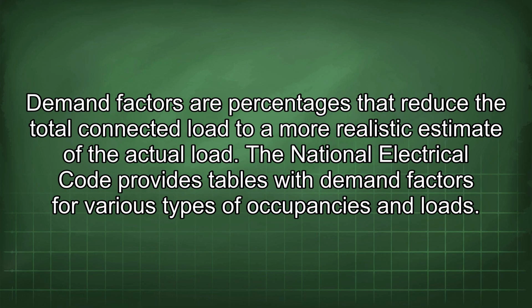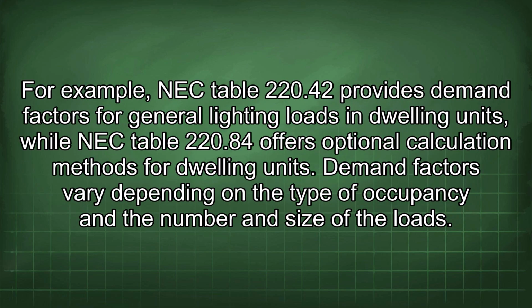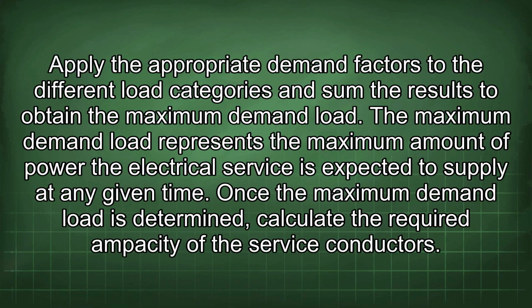Demand factors are percentages that reduce the total connected load to a more realistic estimate of the actual load. The National Electrical Code provides tables with demand factors for various types of occupancies and loads. For example, NEC Table 220.42 provides demand factors for general lighting loads in dwelling units, while NEC Table 220.84 offers optional calculation methods for dwelling units. Demand factors vary depending on the type of occupancy and the number and size of the loads. Apply the appropriate demand factors to the different load categories and sum the results to obtain the maximum demand load.